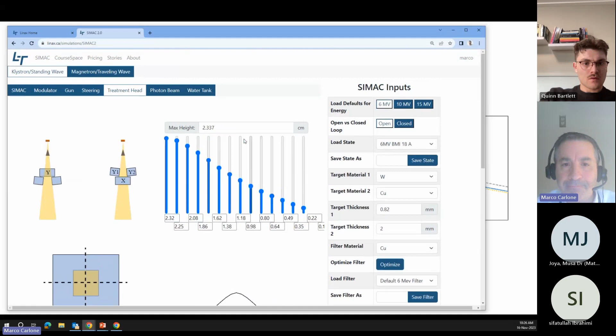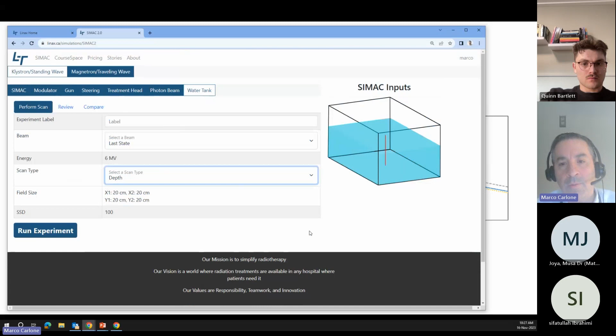Now these tabs over here simulate the operation of the accelerator and what the result is. The water tank screen now simulates the QA device, which in this case is a standard water tank that you'd use for annual QA. So we can pull in some beams that we've measured before, which are the beams I've created, and then we can do profiles either cross plane, in plane, or depth dose profiles, and then we can label these and review them afterwards.